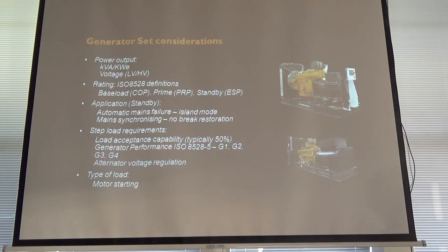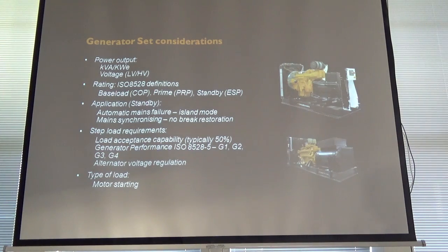So if you've got 11 kV generators supplying power in a ring, once you've got the loss of mains and the start signal, the specification requires that you're supplying power at LV level. So the generators close onto a bar, they supply the power to energise the transformers, who in turn have their breakers closing, and that's supplying the power at LV level within 15 seconds. And it's proven time and time again you can do that.